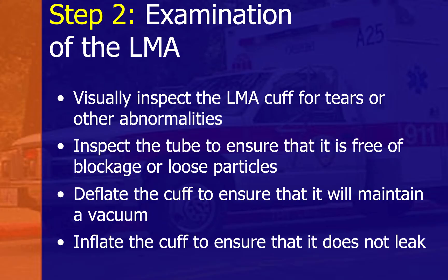Examination of the LMA: inspect the cuff for tears and other abnormalities, inspect the tube to ensure it is free of blockage or loose particles. Deflate the cuff to ensure it will maintain a vacuum, then inflate the cuff to ensure it does not leak.